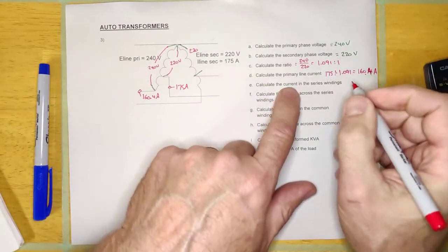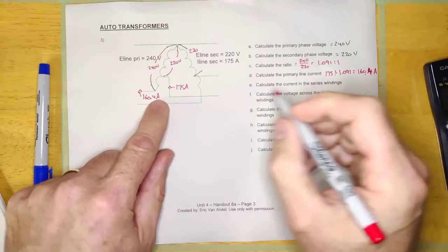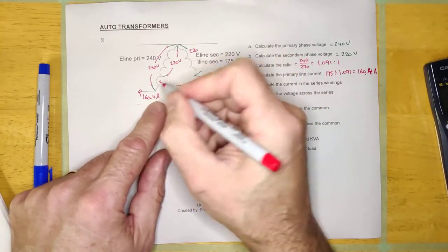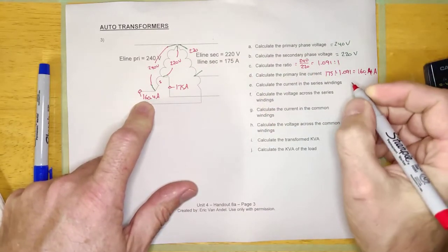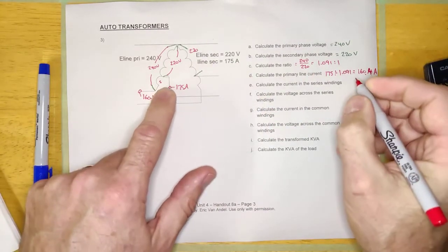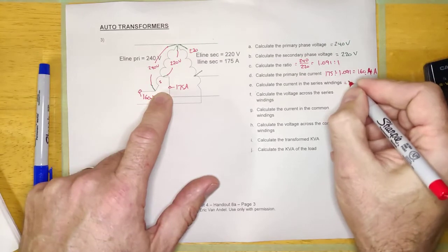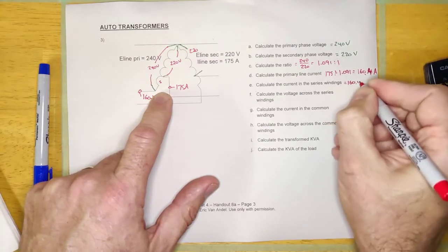Calculate the current in the series winding. There's the series winding right there, that little guy, one bump. It has to be equal to the primary current because it always will be. It's always out here in series with the primary, so this is just 160.4 amps.